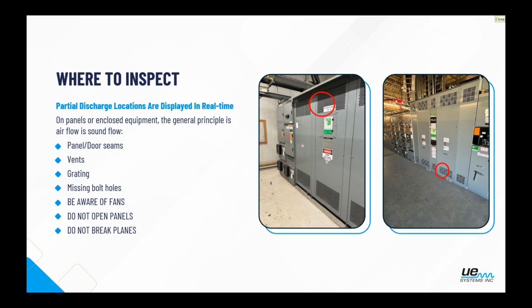An example would be the 480 lighting transformers that everyone has, in the shop next to the wall, probably with a couple of lunch boxes sitting on them right now somewhere. We can inspect from that vent on the top, but we're absolutely not inserting any equipment into that or making contact. And the biggest thing about it, where I have these circles drawn on these two images, is I would strongly recommend inspecting from every point that you can.